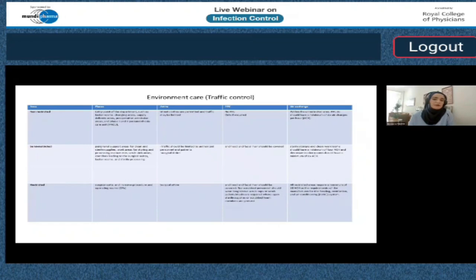And we come to the last zone, the third zone, which is the restricted area. It is the surgical suites where you do the operation and invasive procedures, and the operating rooms. You need to have proper surgical attire, and all the head and facial hair should be covered. Non-scrub personnel should wear long sleeve scrub tops, mainly if we are doing the prepping. A mask is required all the time where open sterile supplies are present. All restricted areas need a minimum of 20 air exchanges, depending on the manufacturer of the heating, ventilation, and air conditioning (HVAC) system.